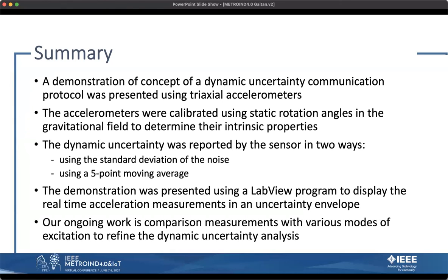And so that therefore the host computers don't need to know or store the specific sensor performance parameters with them. Instead, the sensor is constantly reporting both the measurement and the uncertainty of the measurement, and then the host computer can take that information and perform whatever analysis it's doing to determine the environmental conditions at the sensor and what the sensors are reporting on the network.